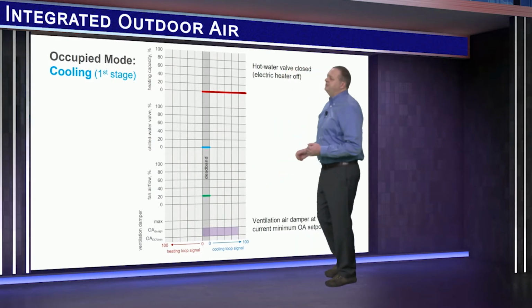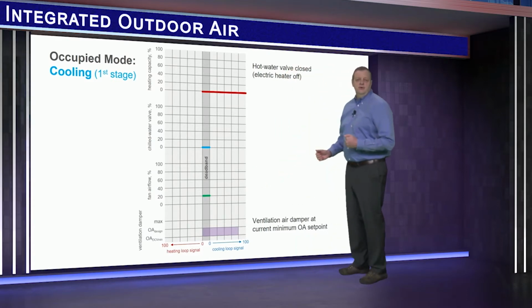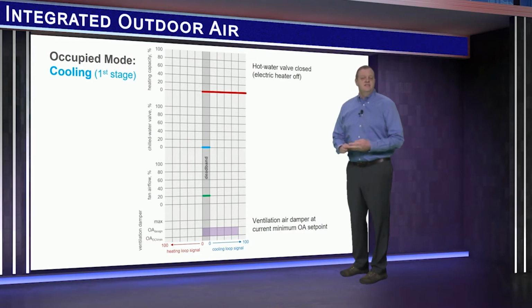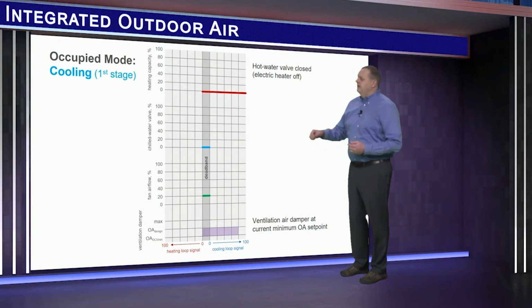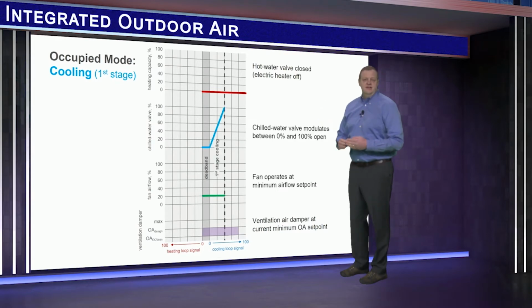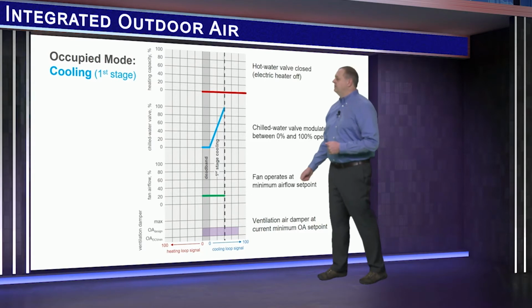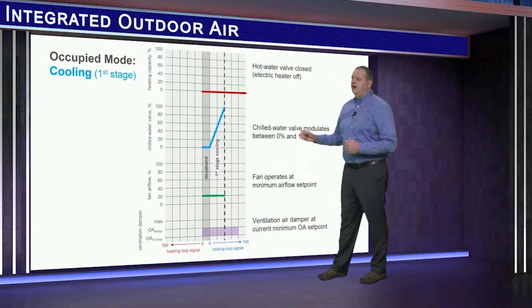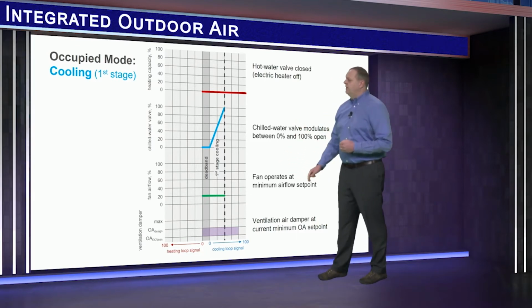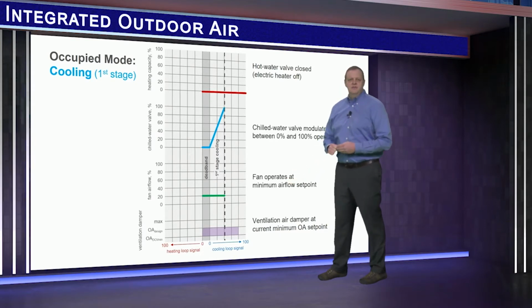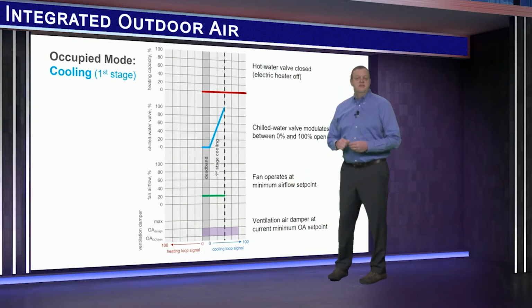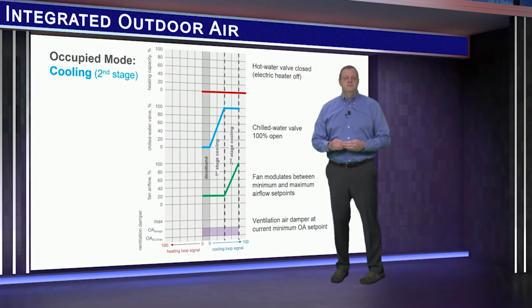Now, when the temperature in the zone rises to the cooling set point, let's say 75 degrees, the controller attempts to maintain zone temperature at this set point by modulating either the terminal fan speed or chilled water valve. The hot water valve or electric heater remains off. Moving from this dead band to the right, the controller first modulates this chilled water valve further open, while the fan remains at its minimum airflow set point. This is the first stage of cooling.